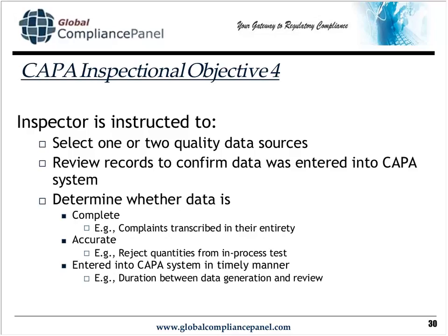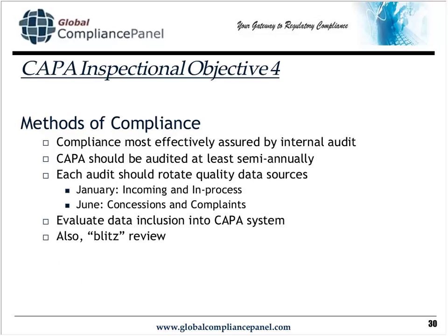Usually it's monthly or quarterly; I've been involved in those 2 CAPA review types of situations. I've never had an FDA inspector tell me that that's not timely enough. I would imagine, though, if you only enter things into your CAPA system for your executive management review, that might be something that the FDA inspector would have an issue with.